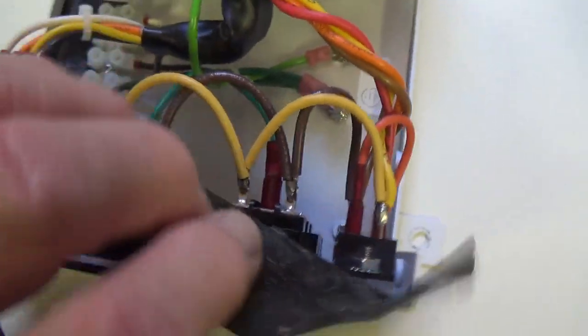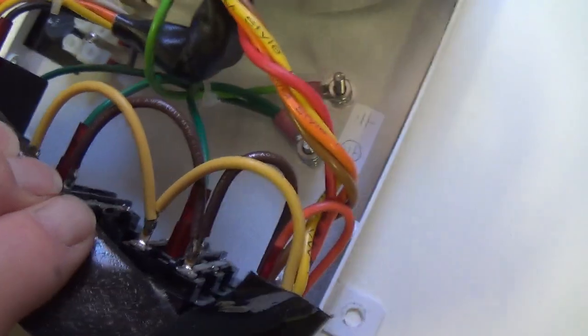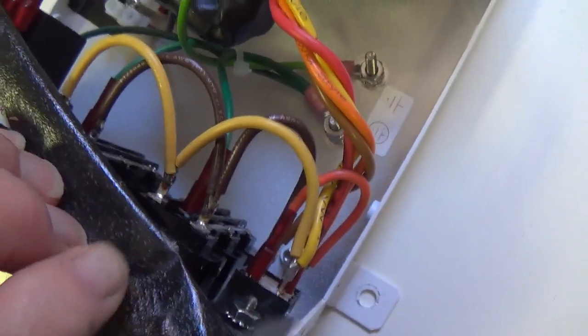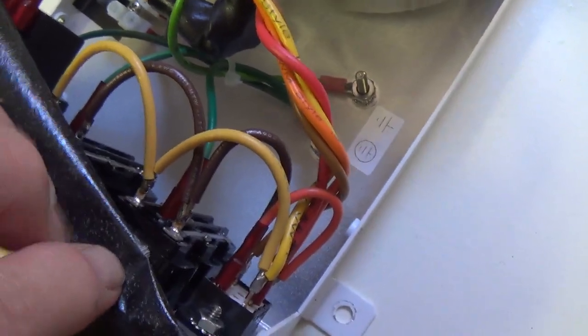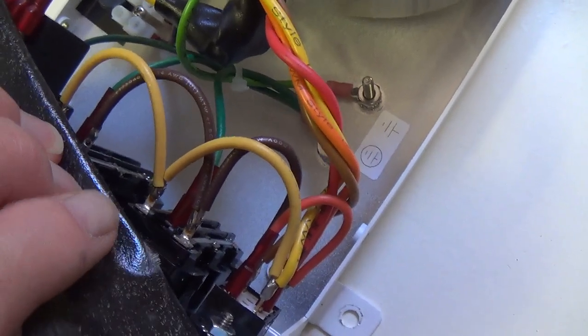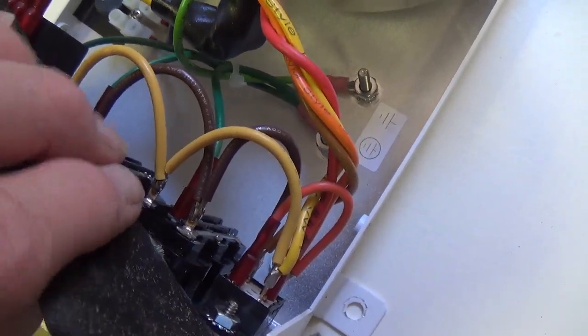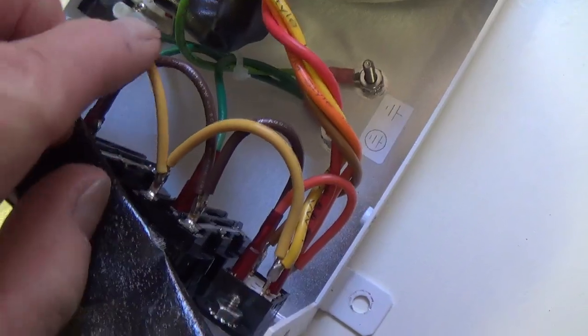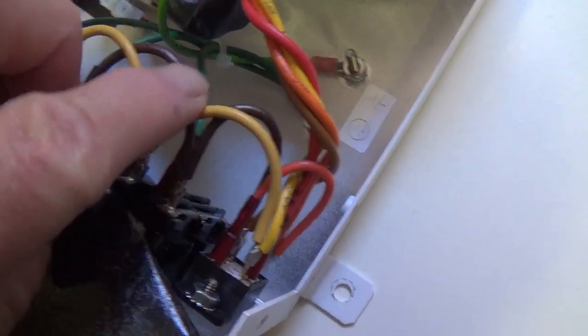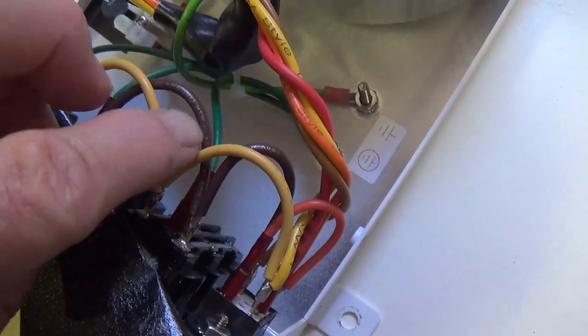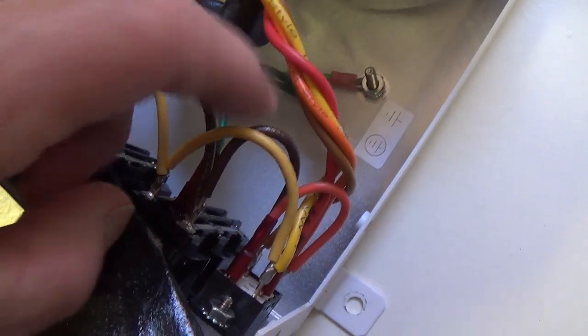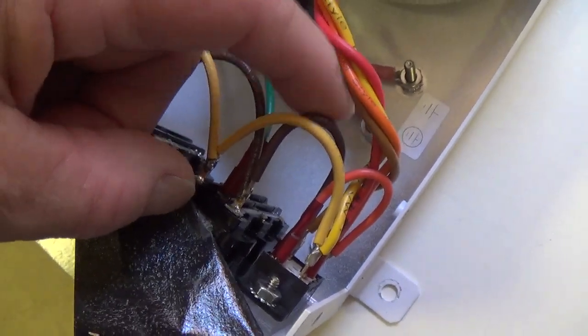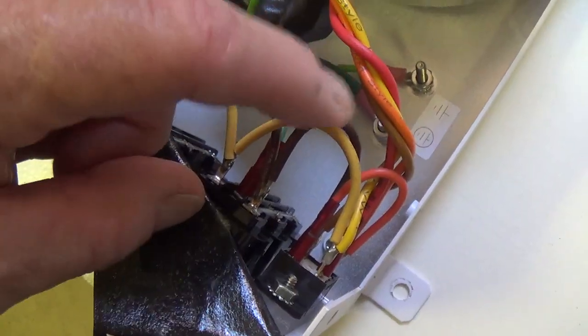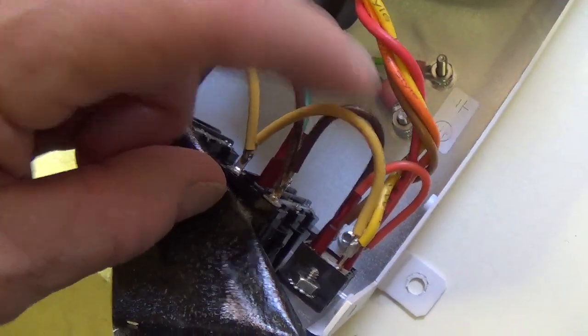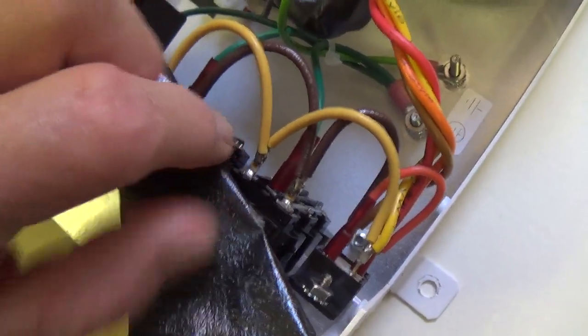I'm going to pull it back to show you where, if your medical grade transformer is not suitable for isolation from ground reference, where yours will be different from this one. And that is right here, the neutral line. It's usually white and the hot line is black. In this, the hot is brown and the neutral or return is sort of a yellowish color.